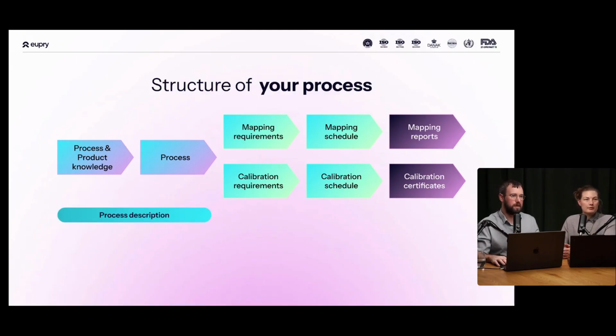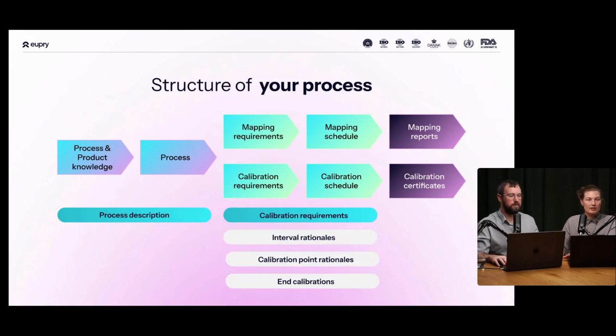So first of all, you need a process description. You need to describe what you are storing, under which conditions, and what it looks like. And then you will need to define your calibration requirements. Among other things, there are the things that we actually talked about already. So we have the calibration interval and the rationale behind it. Is it because we want to make sure that we have the risk area covered? If your temperature reaches above the interval that you expected for storage, then you need to know that your sensor can measure within these intervals.